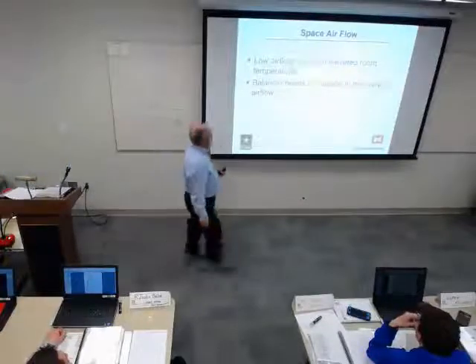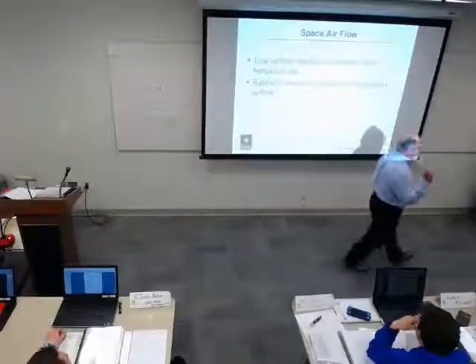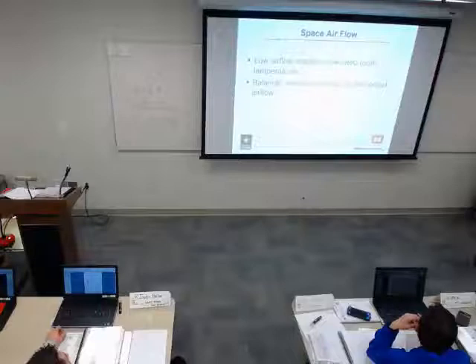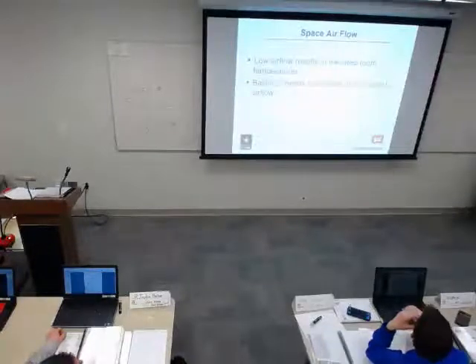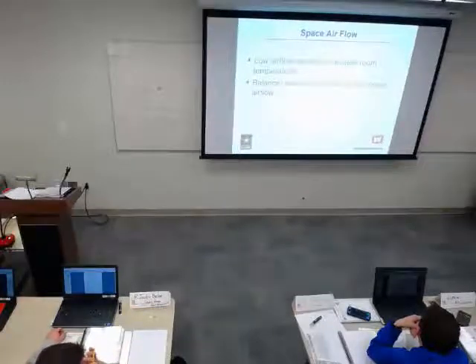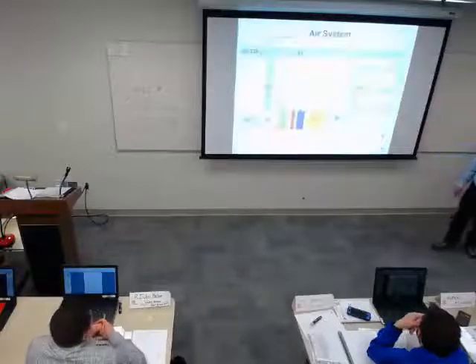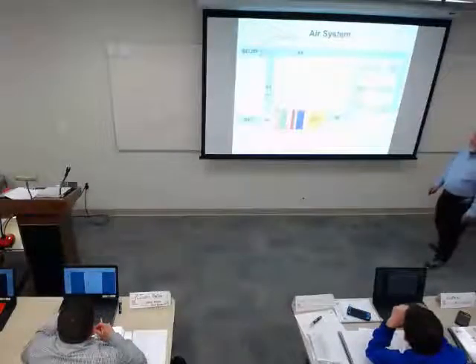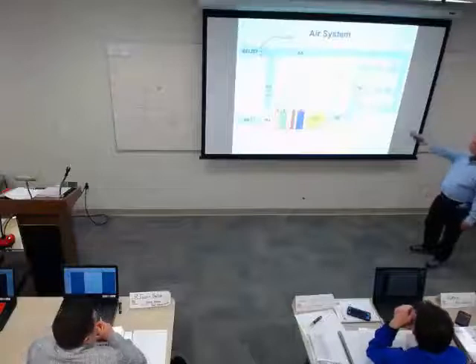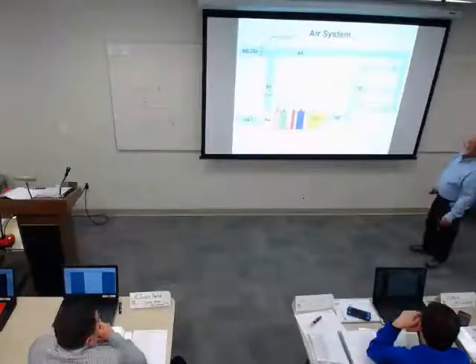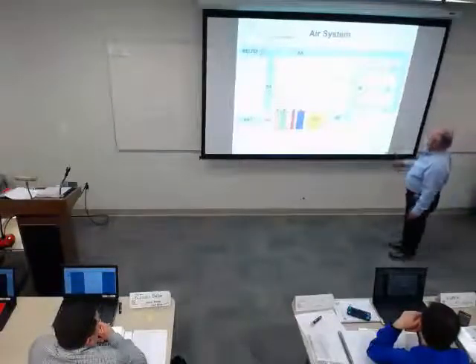There you go. All right, so all airflow is not good. We count on about a 20-degree rise through a room, and that's based on the airflow we've calculated for that room. If we don't get that airflow, we're going to have either more than 20 degrees or less than 20 degrees. So we need to have the correct airflow. So here is an air system. This happens to be what we call a VAV system, and I'm going to start here in the room.